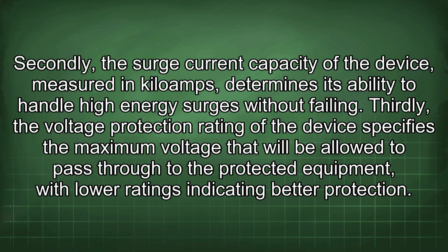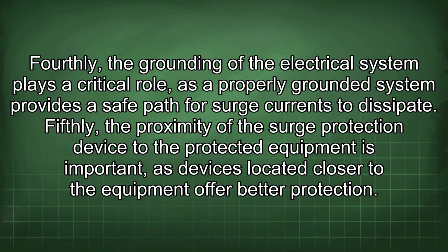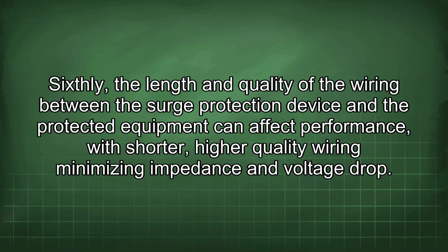Secondly, the surge current capacity of the device, measured in kiloamps, determines its ability to handle high-energy surges without failing. Thirdly, the voltage protection rating of the device specifies the maximum voltage that will be allowed to pass through to the protected equipment, with low ratings indicating better protection. Fourthly, the grounding of the electrical system plays a critical role, as a properly grounded system provides a safe path for surge currents to dissipate. Fifthly, the proximity of the surge protection device to the protected equipment is important, as devices located closer to the equipment offer better protection. Sixthly, the length and quality of the wiring between the surge protection device and the protected equipment can affect performance, with shorter, higher quality wiring minimizing impedance and voltage drop.